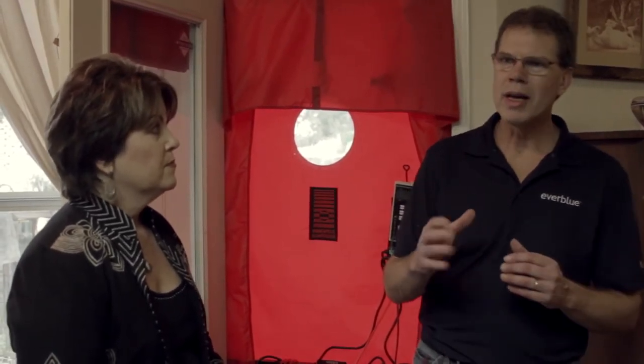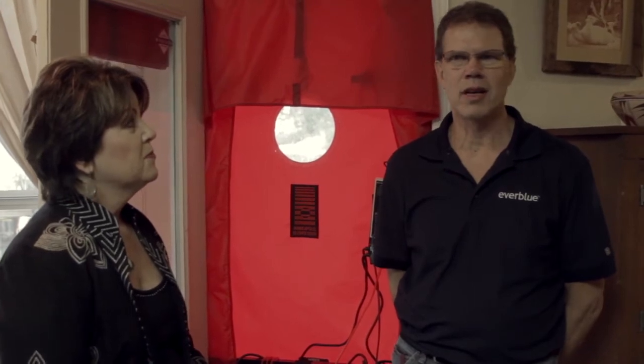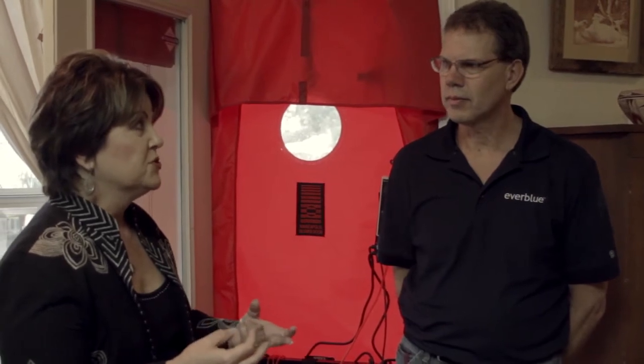But yeah, we take it a step farther now because we have infrared. Yes. So we'll use our infrared cameras. The blower door, of course, exaggerates the leaks into the home, and we'll either be pulling hot air in or cold air in based on the time of year. Then we'll get a much more defined reading on our infrared camera. So we've taken it a step farther. Smoke pencils are a good tool for the customer to see where the leaks are, but the infrared helps us see things that you just can't see with the smoke pencil or with the naked eye. And actually, I think on my 2004 or 2005 audit, he did use that, and in fact he also checked for moisture. He had a moisture meter as well.